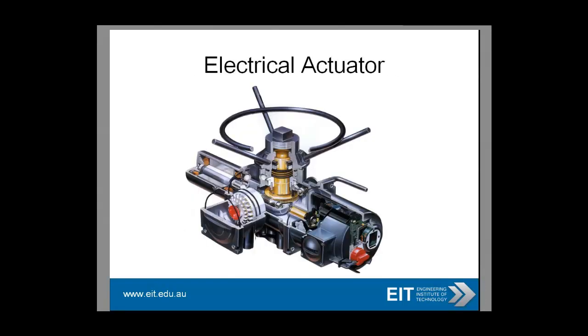Moving beyond pneumatic, what about an electric actuator? An electric actuator does not require clean air — it just requires electricity. It's used where other actuators are not practical, and the technology is continuously improving; have a look at how small they've become. Often they have a hand wheel and limit switches as standard. However, they are still pretty slow in certain applications, don't always have a fail-safe action, are not great for modulating control, can be expensive, and are difficult to maintain. You would not use them in explosive areas due to elevated voltage risks.